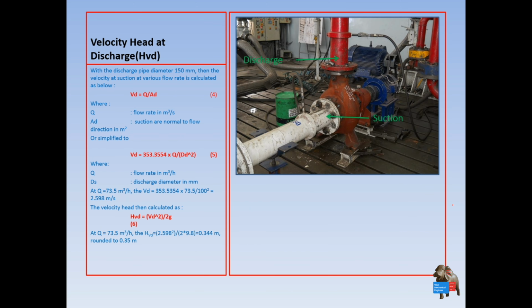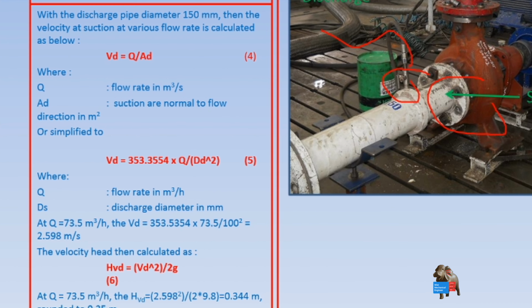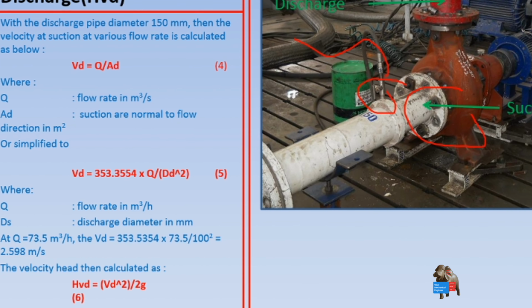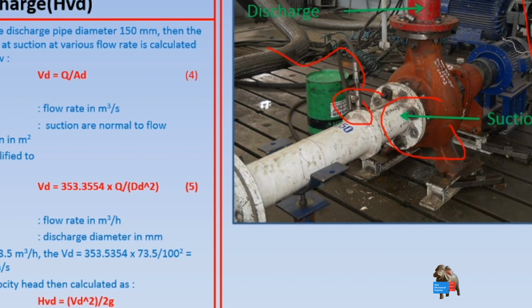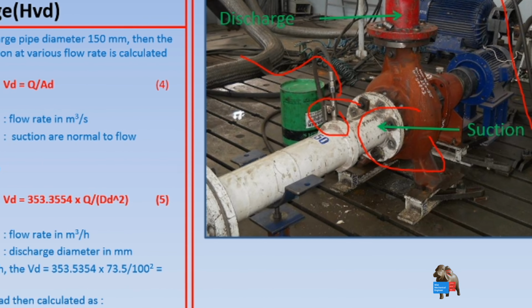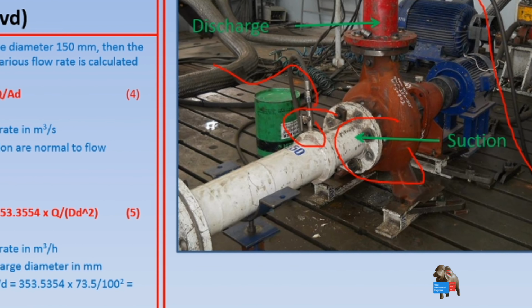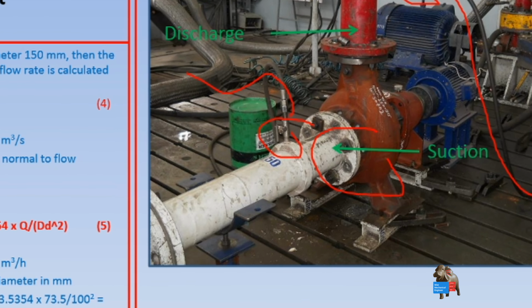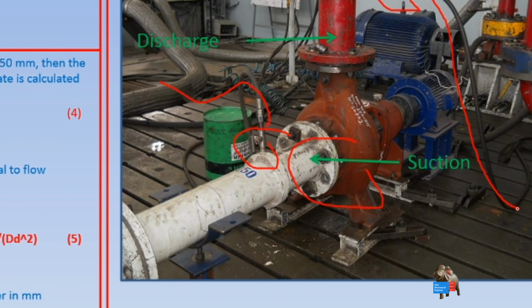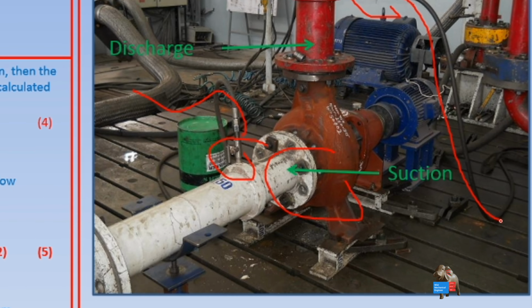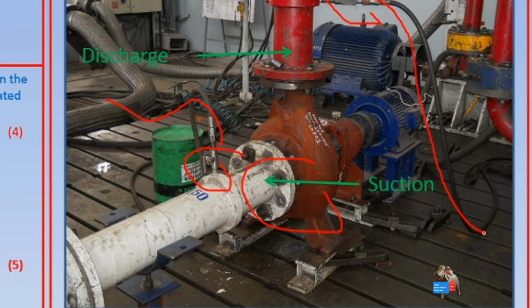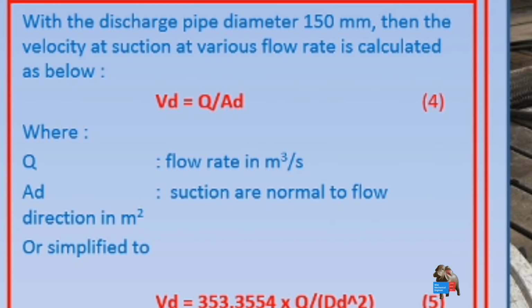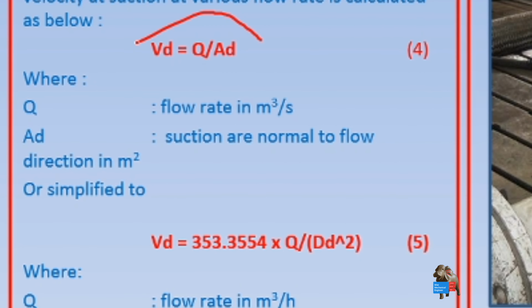Okay, this is another clear view of how the pump runs during the testing. This is the suction. This is the pipe tapped to a pressure transducer, which here is already a digital pressure transducer. In the past they used manometers to measure the static pressure at suction and at discharge. Now they do it electronically, and then you calculate, of course, the velocity head at discharge using this formula.